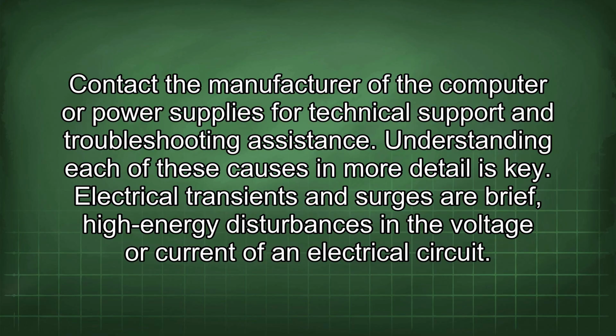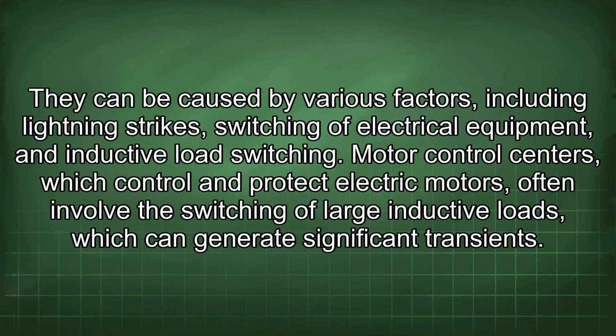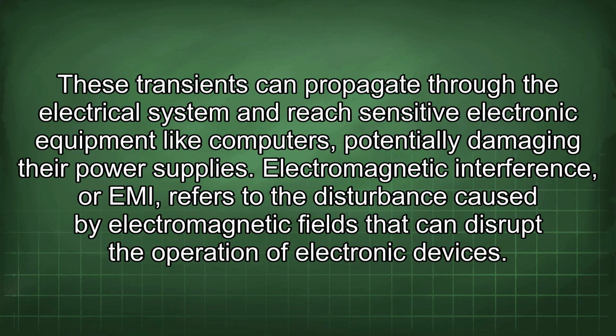Electrical transients and surges are brief, high-energy disturbances in the voltage or current of an electrical circuit. They can be caused by various factors, including lightning strikes, switching of electrical equipment, and inductive load switching. Motor control centers, which control and protect electric motors, often involve the switching of large inductive loads, which can generate significant transients. These transients can propagate through the electrical system and reach sensitive electronic equipment like computers, potentially damaging their power supplies.